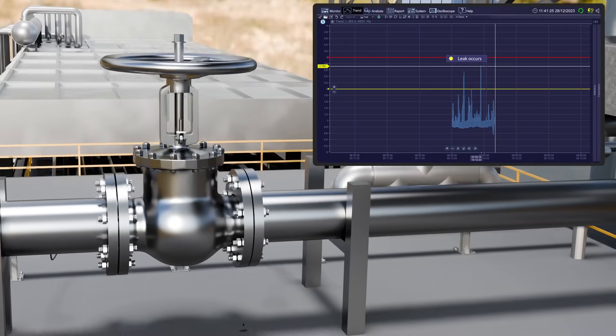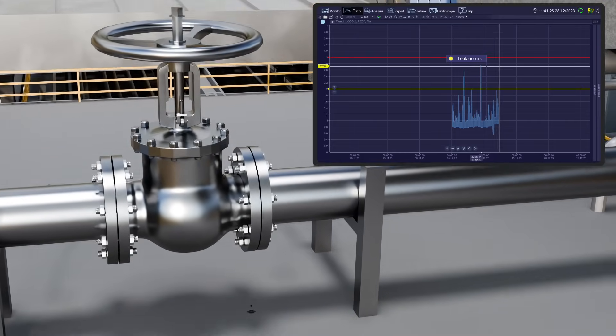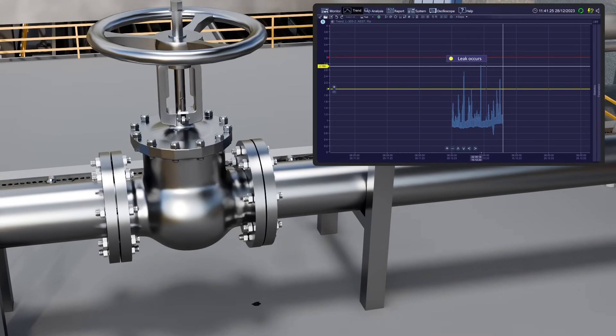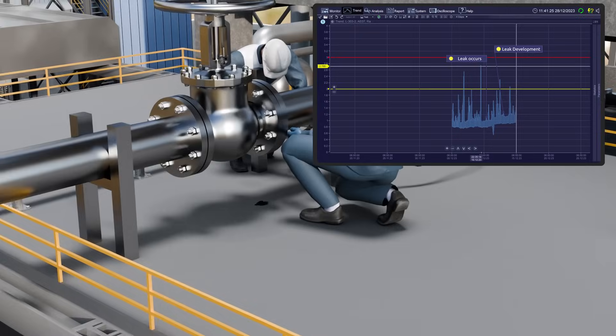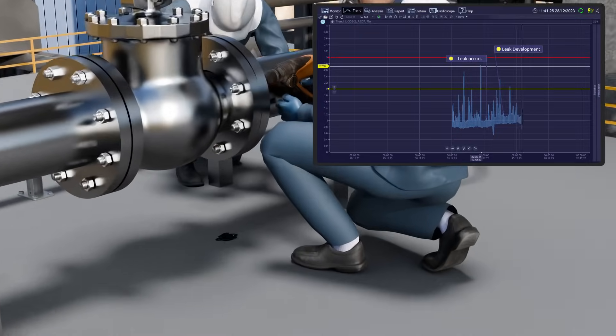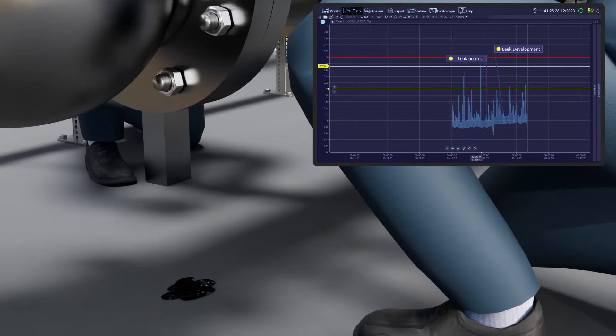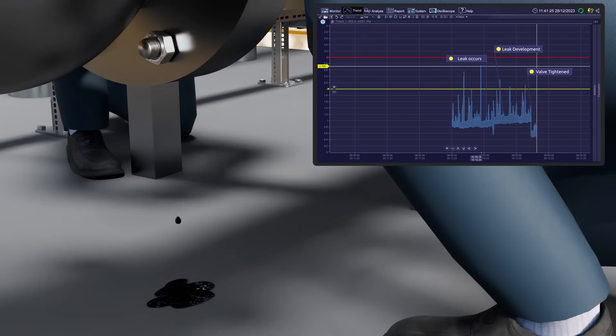From December 5th to December 15th, the leak gradually increased while the system monitored the trend of the acoustic emission parameter, recording its consistent growth. Between December 15th and December 20th, the maintenance team tightened the shutoff valve, which reduced the leakage but did not eliminate it completely.